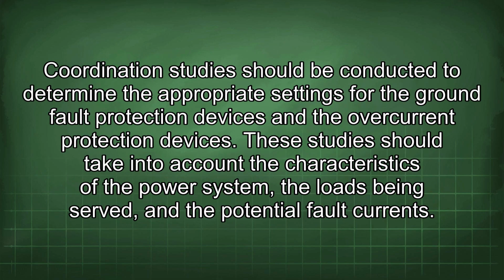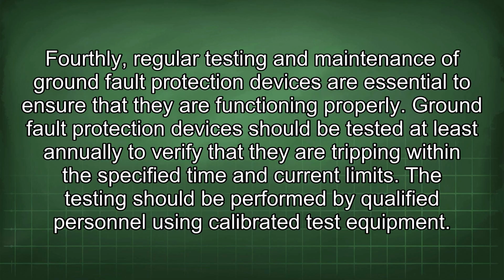Coordination studies should be conducted to determine the appropriate settings for the ground fault protection devices and the overcurrent protection devices. These studies should take into account the characteristics of the power system, the loads being served, and the potential fault currents. Fourthly, regular testing and maintenance of ground fault protection devices are essential to ensure that they are functioning properly. Ground fault protection devices should be tested at least annually to verify that they are tripping within the specified time and current limits. The testing should be performed by qualified personnel using calibrated test equipment.